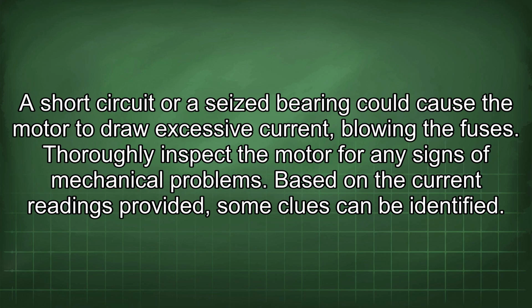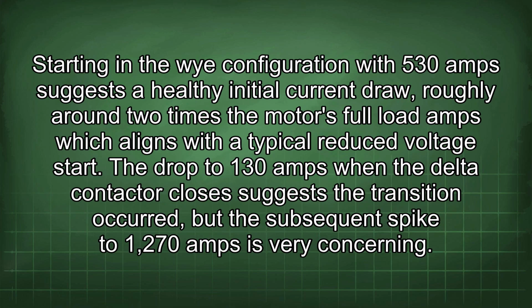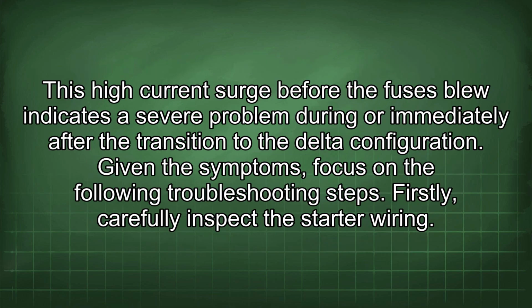Based on the current readings provided, some clues can be identified. Starting in the Y configuration with 530 amps suggests a healthy initial current draw, roughly around 2 times the motor's full load amps, which aligns with the typical reduced voltage start. The drop to 130 amps when the delta contactor closes suggests the transition occurred, but the subsequent spike to 1270 amps is very concerning. This high current surge before the fuses blew indicates a severe problem during or immediately after the transition to the delta configuration.